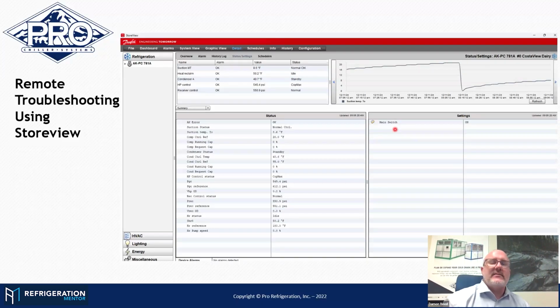I don't recommend changing many settings remotely or without access to somebody on site, because it is easy to make a setting change, not get the expected result, put the system into an alarm, change your setting back because you're like, okay, that didn't do what I expected it to do, but now what? Now I got to get a hold of somebody.